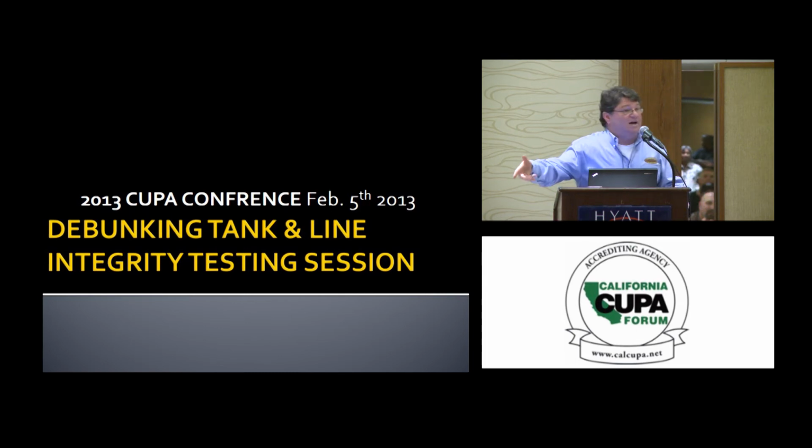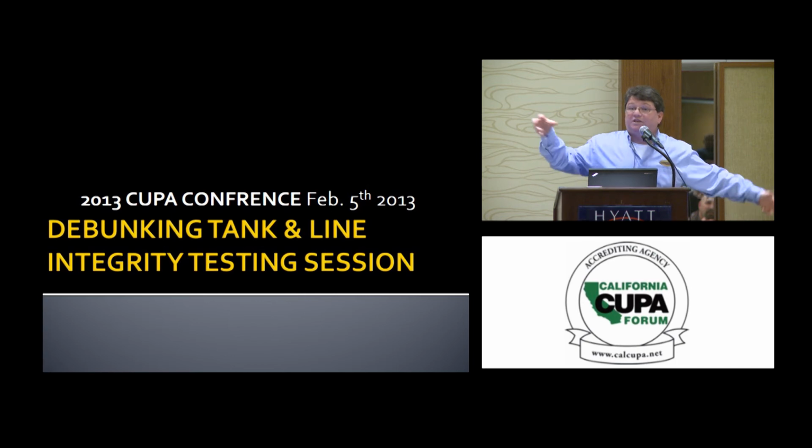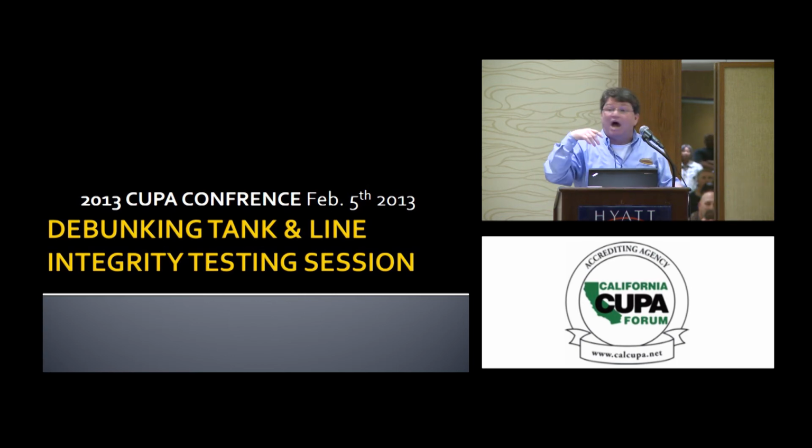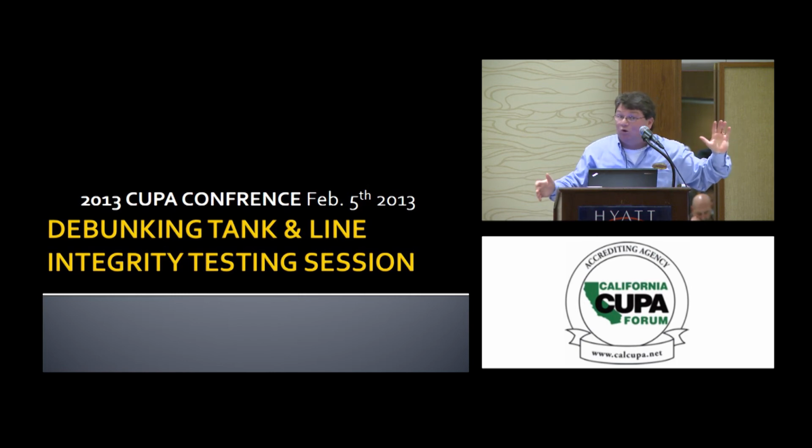When you see that guy getting $1.85 in Compton, hang on to the flex connector and you're going to feel that thing just shaking every time he hits the handle off. It's like a shock, a water hammer or a hammer effect on that line. And if that thing has got over a 40-degree angle, which is what it's not supposed to be over, now you're starting to bend it.